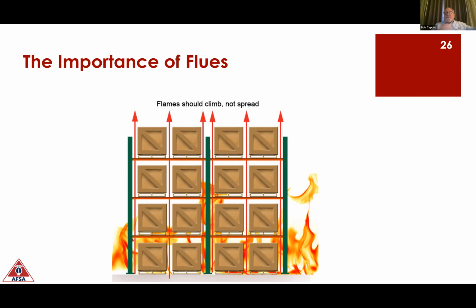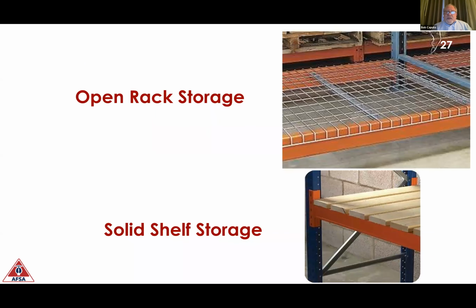Okay, because in the pallet rack, we want the flames to climb, not spread horizontally. That's going to become more challenging. So if I have the pallets too close, or if I have solid shelving, it's going to force the fire to expand or grow horizontally instead of vertically. But my best scenario is to have those flue spaces that allow the flames and the heat to climb, and then the water from the ceiling sprinklers to cascade down through those unit loads and get water to the base of the fire. And frankly, the quicker we do that, the better off we are, because the faster we do it in the timeline, the less heat release rate we have, the smaller fire we have.